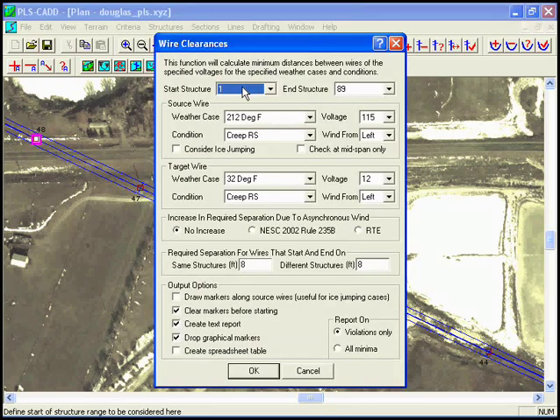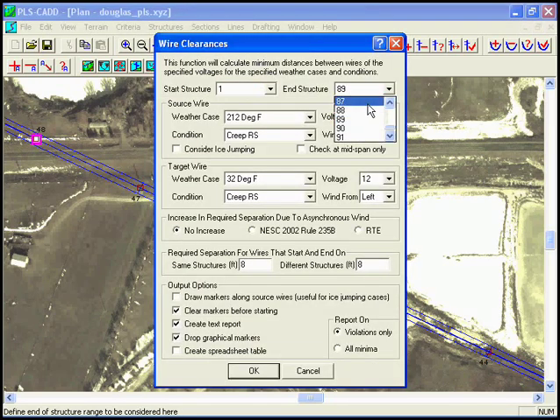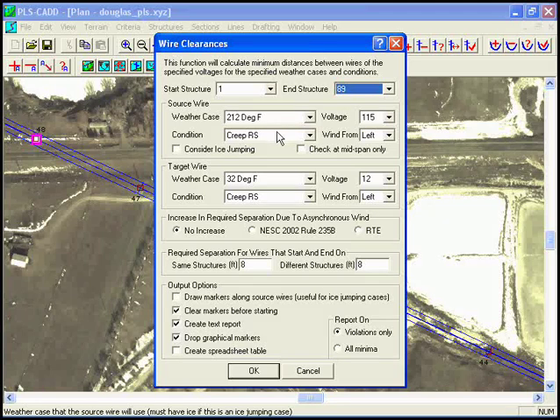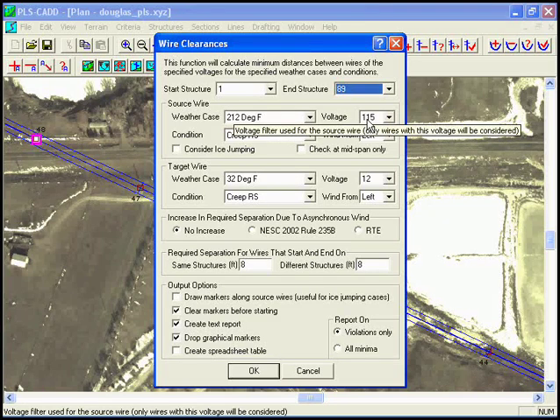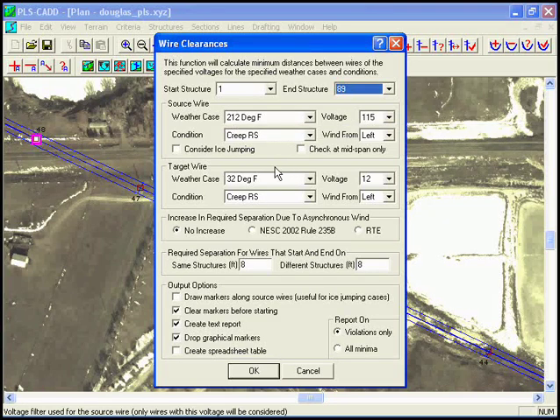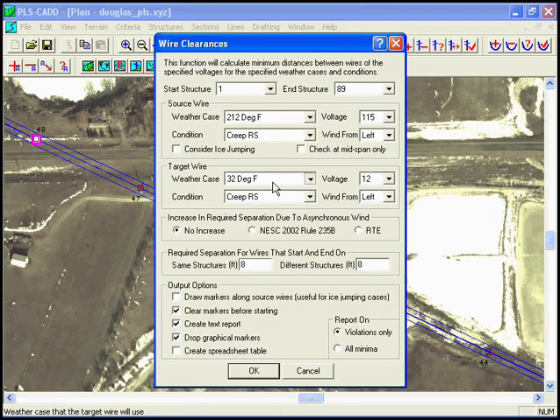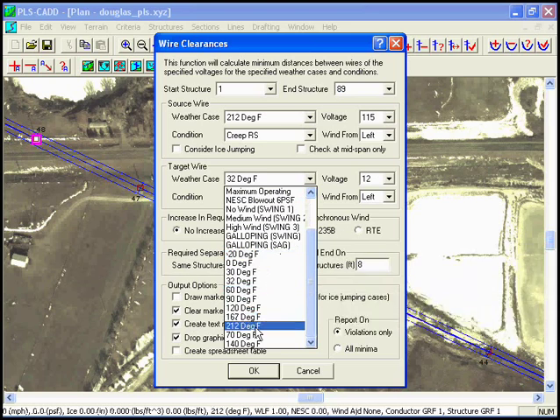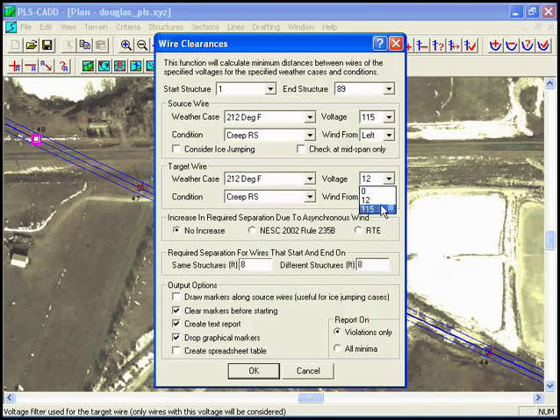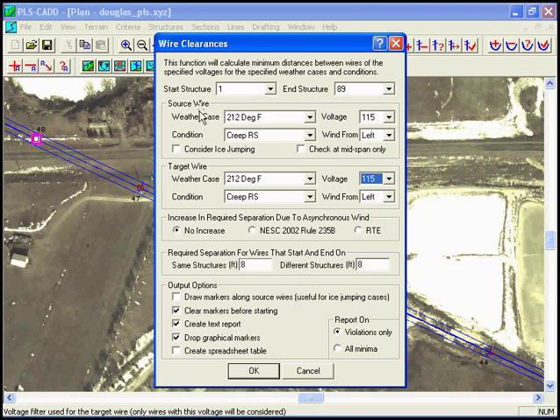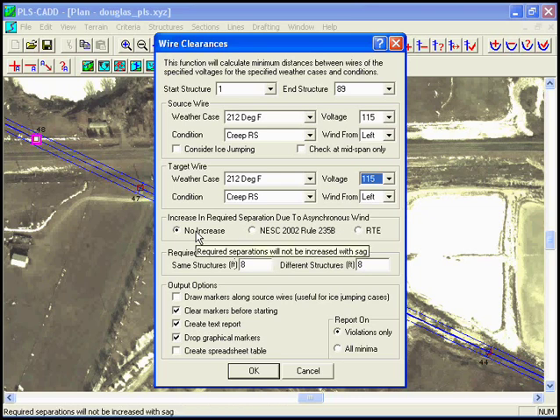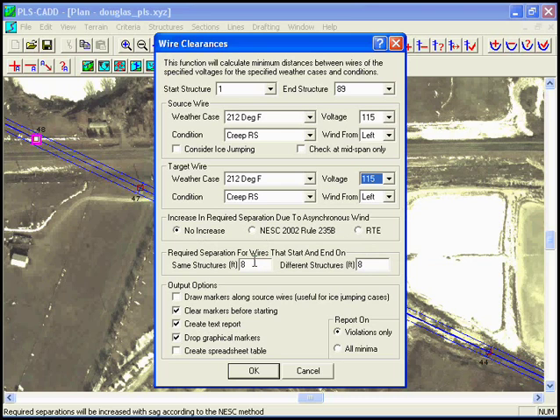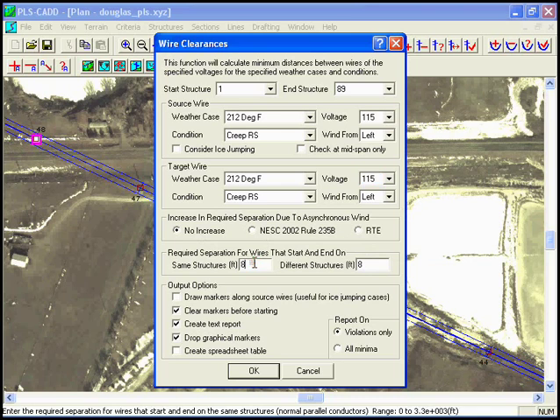Then we're going to go from structure 1 to structure 89 if we wanted to do other parts of the line we could. We're going to go from 212 degrees F after creep underneath a 115 kV, and we're going to check that to our 212 degrees F after creep underneath our 115 kV. So we'll be doing a phase to phase check within the 115 kV circuits. We're not going to require any kind of increase in mid-span. If we wanted to use the NESC increase we could certainly add that in here. Then we're going to say that we need eight foot of clearance between the 115 kV phases on the same circuit as well as on separate circuits.